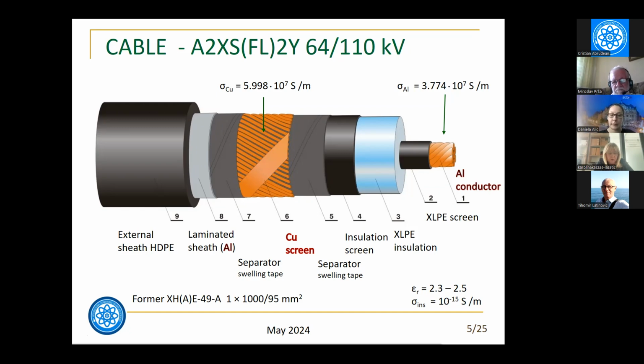Due to the high-voltage cable construction, that means due to the metal electric screen embedded in the single high-voltage cable, it is expected that the electric field outside the shield can be neglected. For this reason, only the magnetic field was taken into consideration in our work. Since the magnetic field depends on the currents inside the cable, the magnetic flux density vector magnitudes were calculated for the maximal load defined by the connected power transformers. The magnetic field distribution was determined for both single cable positions, flat and trefoil.